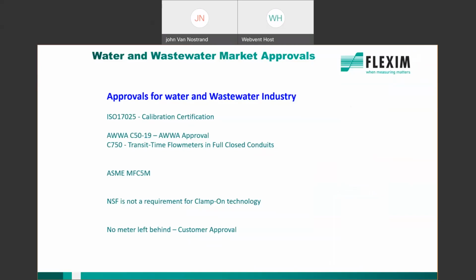So some of the approvals that are important for the water market and wastewater market would be the calibration certificate for sure, and then the C750, which is the American Water Works standard for ultrasonic flow measurement. I'm very familiar with this because I'm on the subcommittee for the C750. And then also the ASME MFC 5M, which I mentioned earlier. That's the American Society of Engineers standard for clamp-on devices using temperature compensation. And again, FLEXIM is the only one that meets that.